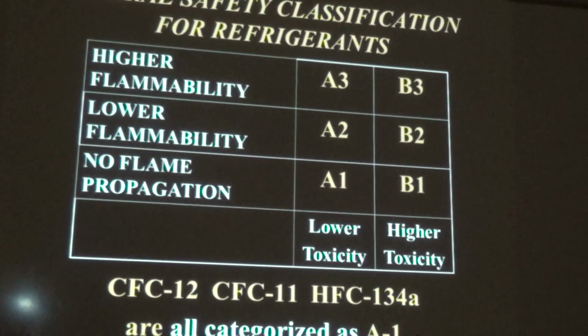Chart, here we go. Got one for you here. A1 means no flame propagation and lower toxicity. So most of the refrigerants, and all the refrigerants except one that I've seen so far on this ESCO Institute test, will be A1. When they ask you about R123, it is the one refrigerant that is a B1. It means there's no flame with that refrigerant, however, it has some toxicity. The bottom line is R123 is the only one that shows up as being a B1 refrigerant.